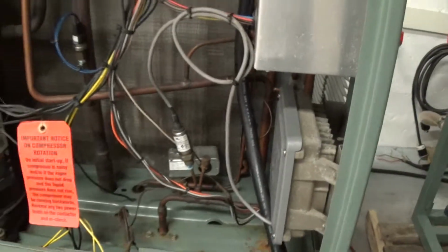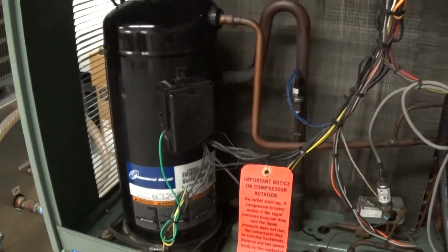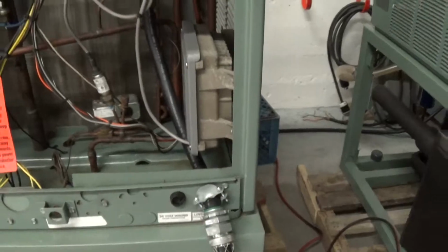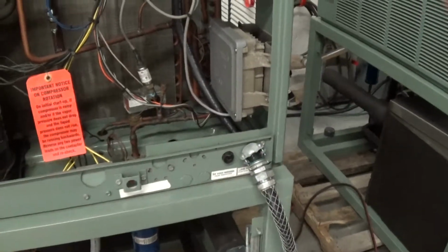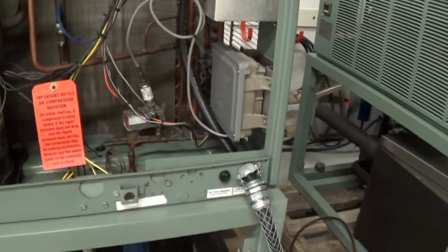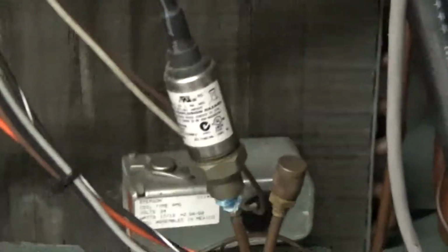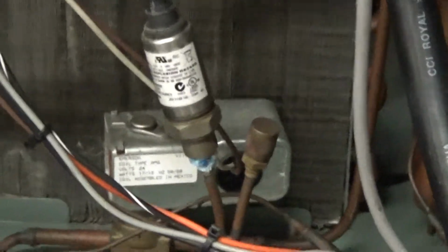So when the compressor is on, which it is right now, the fan isn't always necessarily going to be running. That is normal. So it's balancing depending on what the pressures are. This unit has a low pressure switch which is rated for lower glycol temperatures.